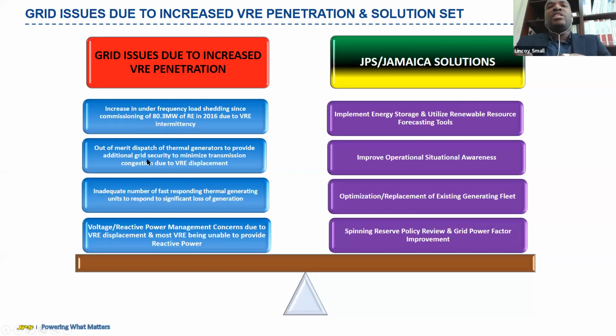That also resulted in us having to do more out-of-merit dispatch - normally you'd try to dispatch the most economic units first. In Jamaica we use least cost optimization for dispatch, so the cheapest units get to the grid first. However, the cheapest units might not be the most agile and robust, and sometimes those gas turbines consume a lot of fuel. We have to bring them online very quickly whenever renewables were dropping off, just to ensure our customers don't lose power.